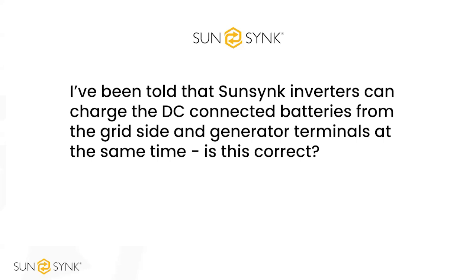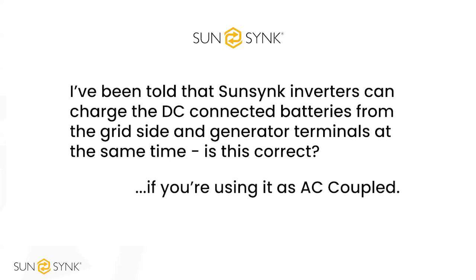All right, so there's a follow-up there. If you're using it as AC couple, yeah, that's right. So if we've got the grid connection, we can charge the batteries from the grid side. Also on the gen input, as I mentioned, we can have that as our AC coupled input. So if someone's got an existing string inverter and they want to connect it straight into us through the gen port, we can charge the batteries from that gen port because we're using it as the AC coupled input, and we can also charge from the gen terminals at the same time.